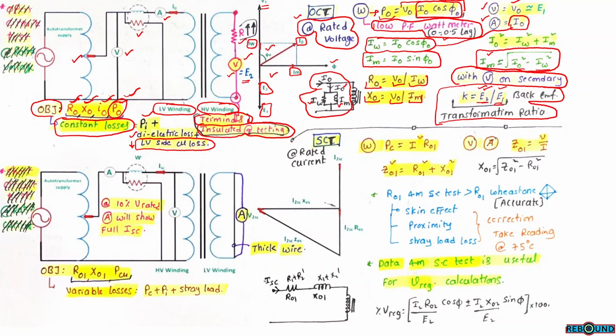Short circuit test. This is the circuit arrangement for the short circuit test. Devices are connected on the HV side and the LV is short circuited through a thick wire, or it may be connected through an ammeter. The objective of the short circuit test is finding R01, X01 and total copper losses. This test gives the total variable losses such as copper losses, a small portion of iron losses and a small portion of stray load losses. The supply is given through an auto transformer.